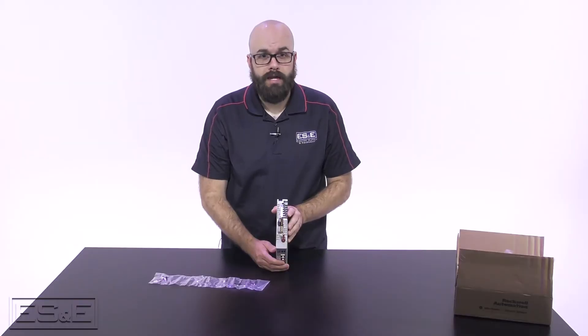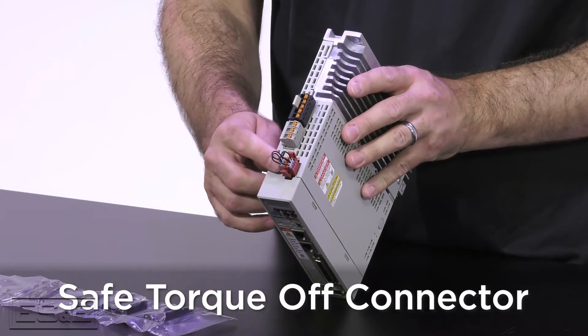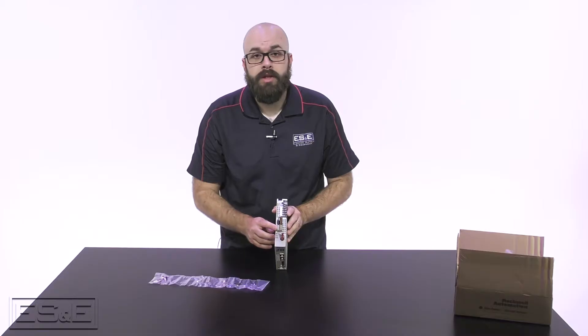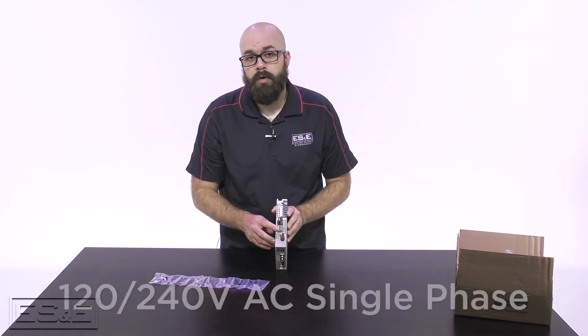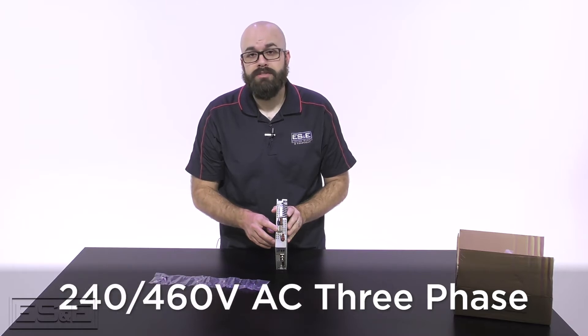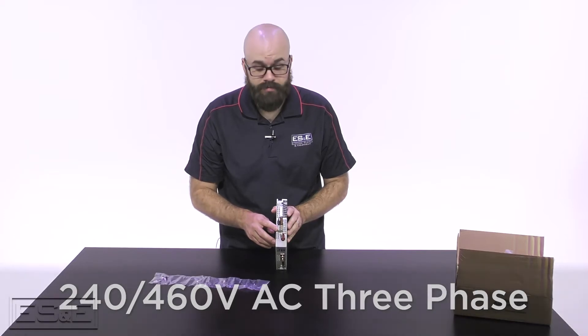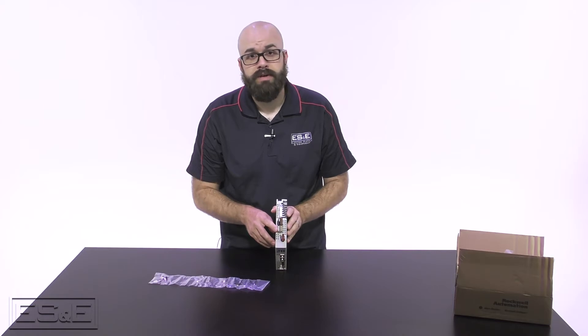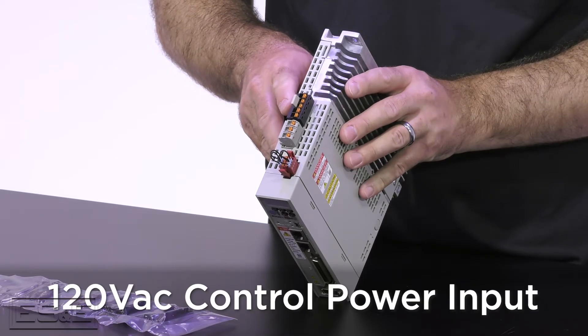On the top of the drive you will find the safe torque off connector and the main input power connector. A note on the input power: the Kinetix 5100 family of drives can be configured for 120 volt and 240 volt AC single-phase, as well as 240 volt and 460 volt AC three-phase. This drive is configured for 120 volt AC single-phase. And then you have the control power input connector.